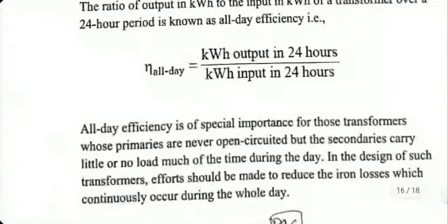All-day efficiency is of special importance for those transformers whose primaries are never open circuited, but the secondaries carry little or no load much of the time during the day. In the design of such transformers, efforts should be made to reduce the iron losses, because iron losses are occurring throughout the day. You try your best to reduce them to improve the all-day efficiency.